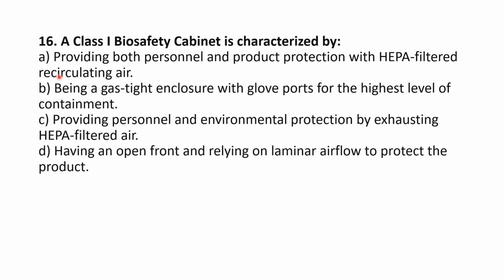Okay, so B, no, not B. Are you saying B? C. Okay, providing personnel and environmental protection by exhausting the HEPA filtered air. So a class 1 biosafety cabinet provides personnel protection by drawing room air in and exhausting it through the HEPA filter, and this one explicitly states no product protection. I think that's my first clue when it comes to class 1 biosafety cabinet. Whenever I remember that there's no product protection, it's easier for me to find the answer among the choices that have been given.